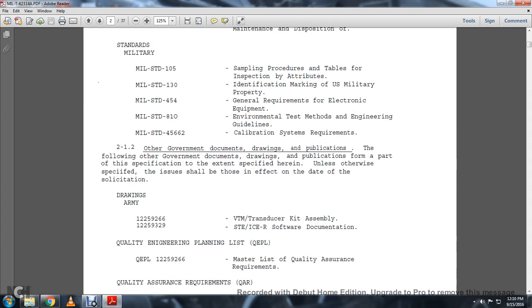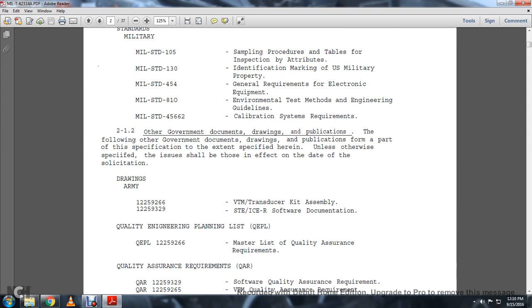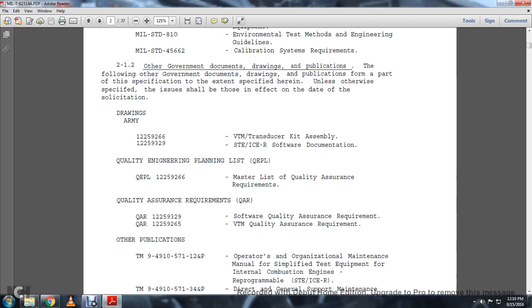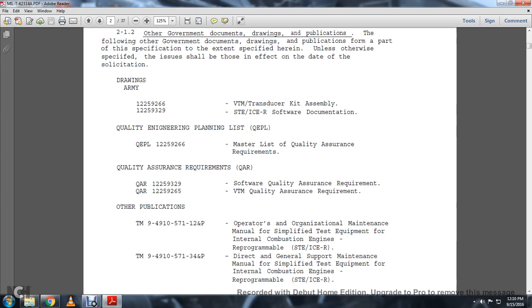2.1.2 Other government documents, drawings and publications. The following other government documents, drawings and publications form a part of this specification to the extent specified herein. Unless otherwise specified, the issue shall be that in effect on the date of solicitation. Drawings, Army: 12259266, VTM transducer kit assembly; 12259329, STE/ICE-R software documentation; quality engineering planning list, or QEPL, 12259266; master list of quality assurance requirements, QAR 12259329, software quality assurance requirements, QAR 12259265, VTM quality assurance requirements.